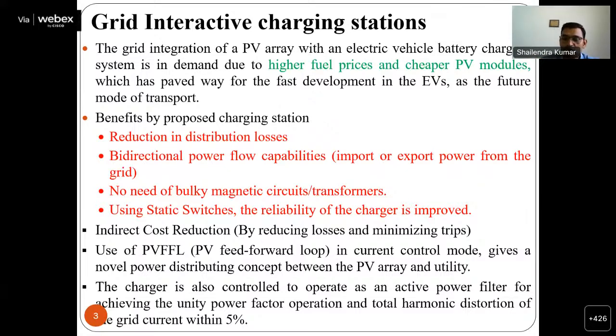The charger is also controlled to operate as an active power filter, mitigating load harmonics when heavy EV loads are put on, since the on-board charger has certain converters and power electronics devices that draw harmonics. This converter, the main body of the system, is utilized to mitigate these harmonics, and the grid current total harmonic distortion (THD) is maintained within 5%, as per the IEEE 519 standard which requires it to be less than 5%.